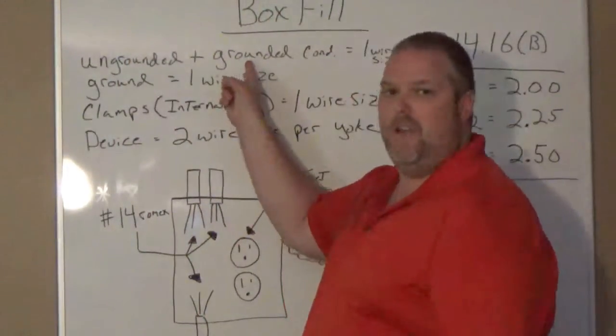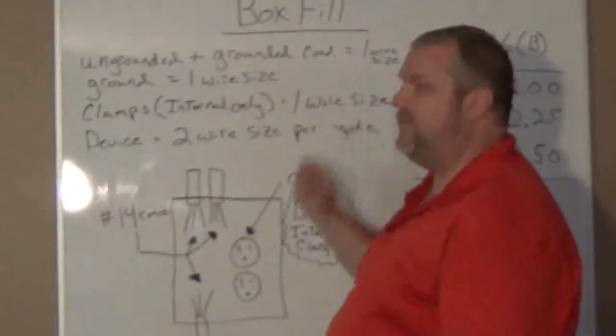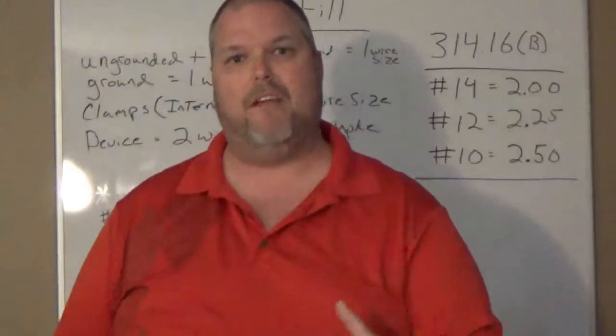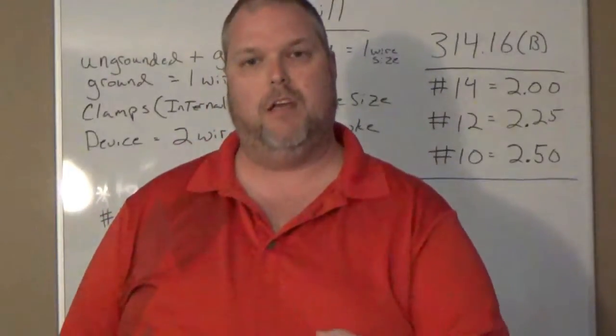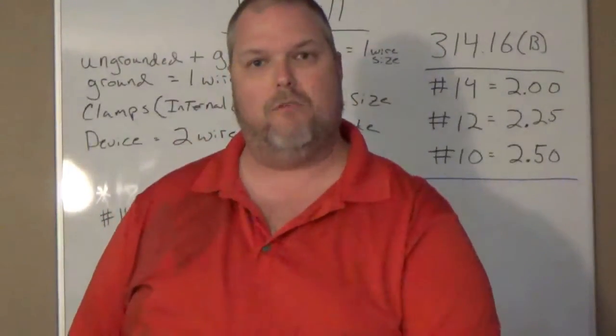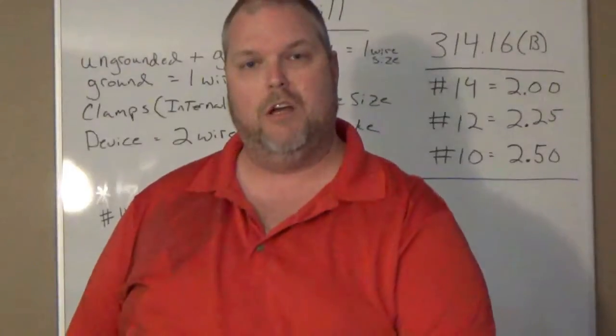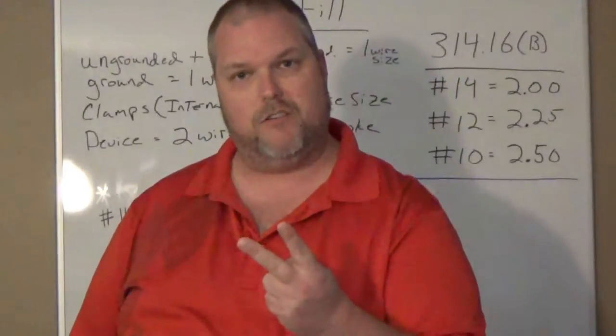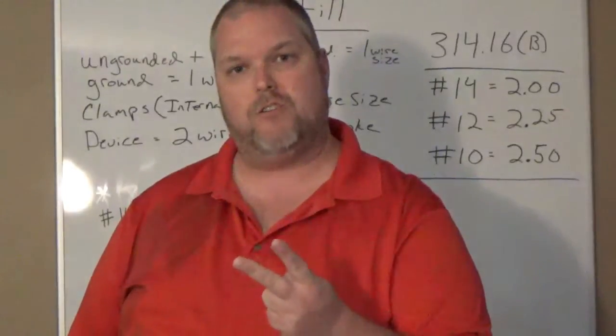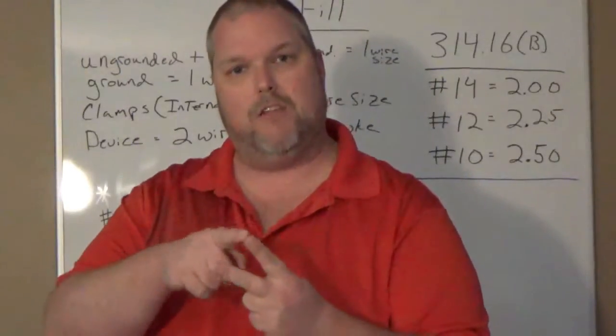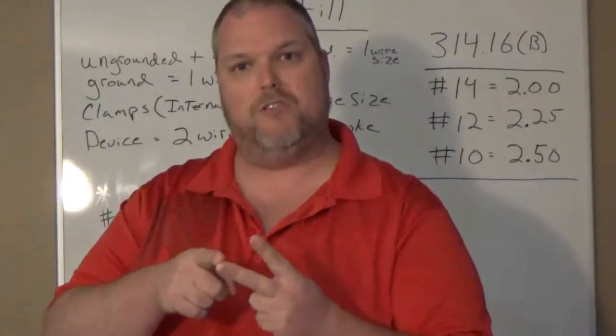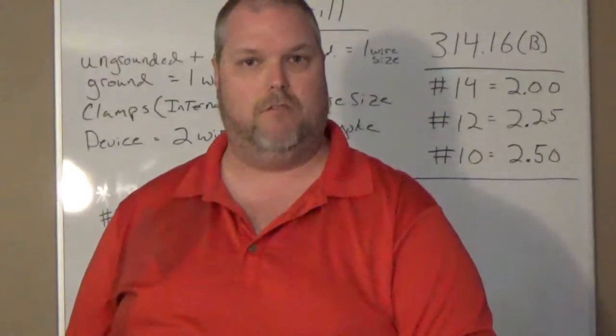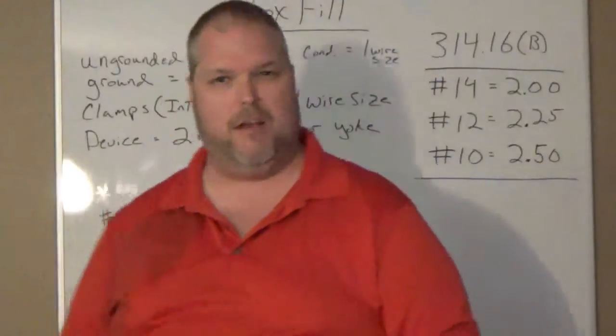Ungrounded conductors and grounded conductors. We count for one wire size. So I'm going to give you this little example. If I have a number 12 conductor, or excuse me, I have a Romex connector. I have two conductors coming in. I have an ungrounded and a grounded conductor. That means I have two conductors. Each conductor, if they're at 12, they're taken at 2.25 and 2.25. So it's actually going to be 4.50. So I hope you guys are following me.